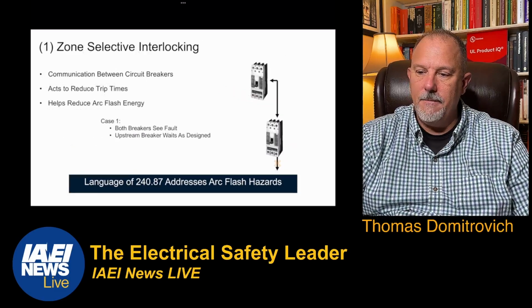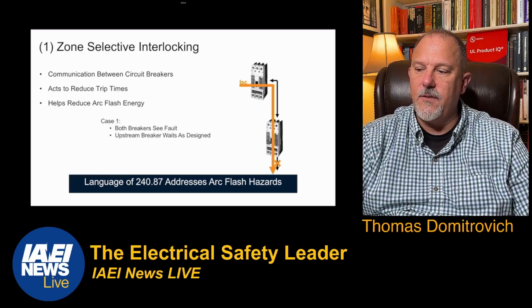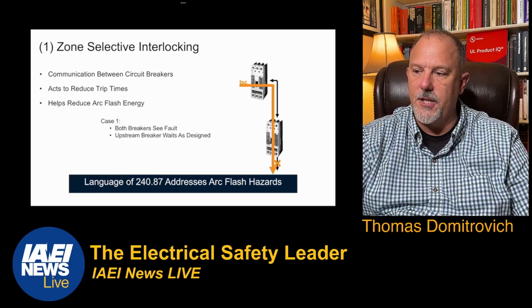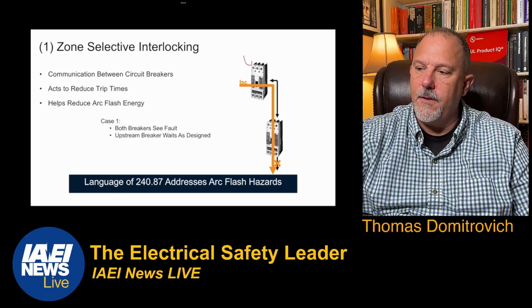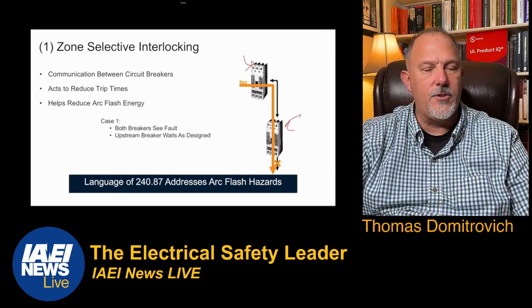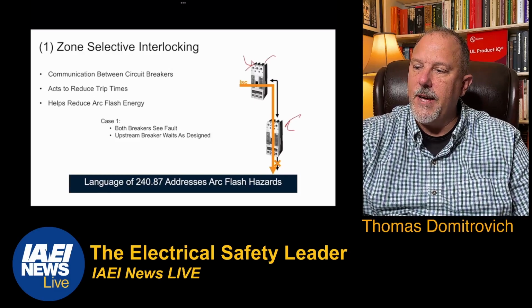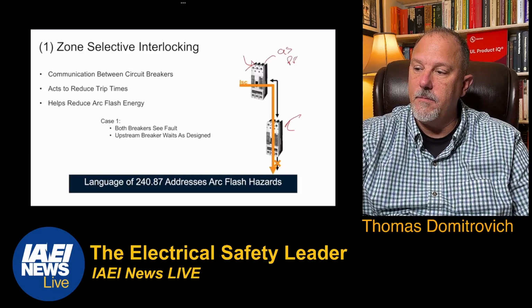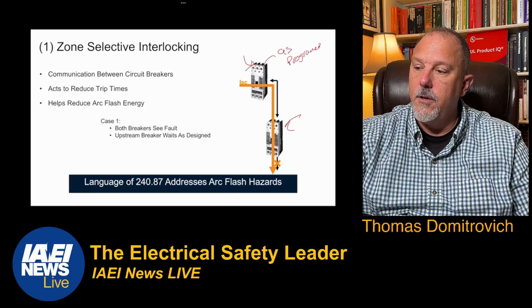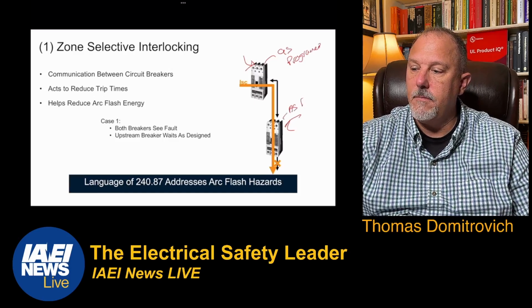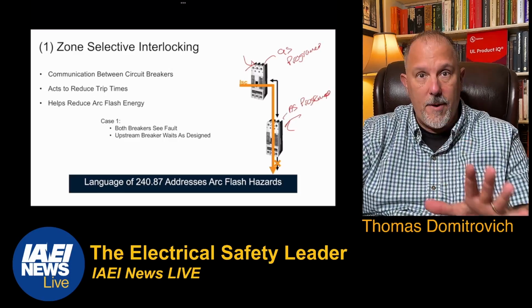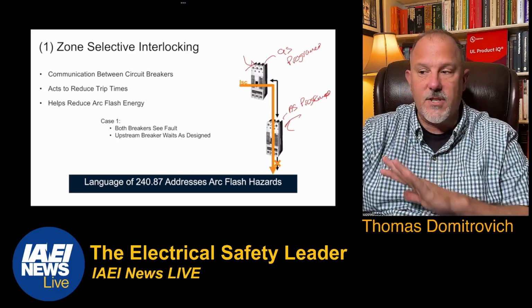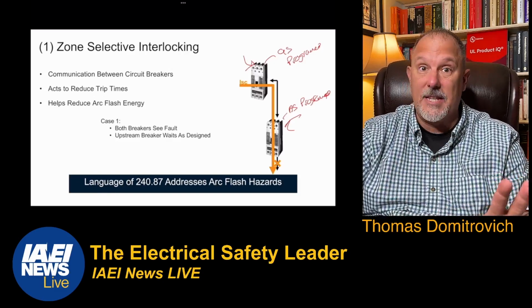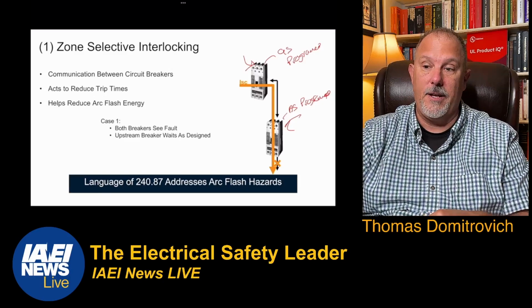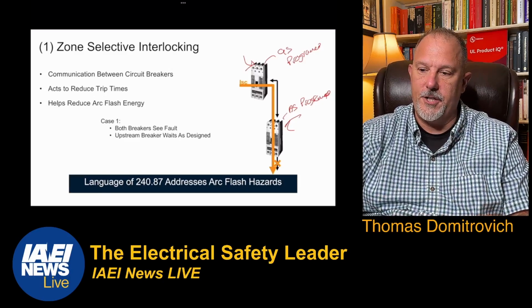Zone selective interlocking. When you have zone selective interlocking, if you have a fault outside of the zone of protection, the current going in the upstream is the same current that goes to the downstream. The upstream device goes as programmed. And remember, if they don't selectively coordinate as programmed, they will not selectively coordinate just because you have zone selective interlocking. ZSI has nothing to do with selective coordination.